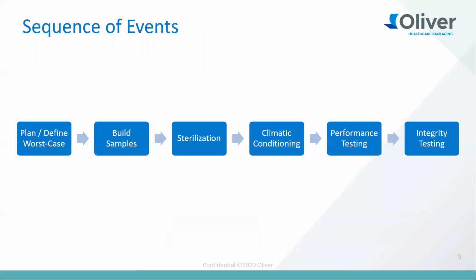So just to talk you through the sequence of events, as Jeremy just spoke about, initially when you do performance testing, you obviously need to have a detailed plan, a good protocol in place, and that protocol is risk-based. So you carry out a risk assessment, and you define your worst case, and you define everything you're going to do, from the transportation to the samples, how many samples you're going to do.